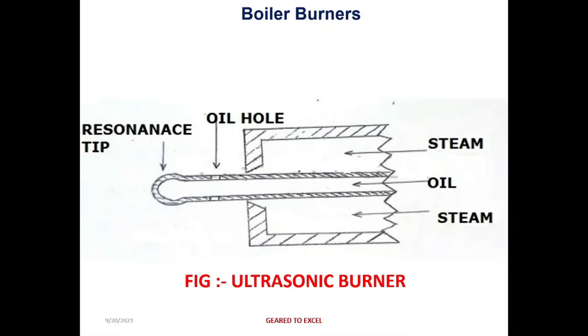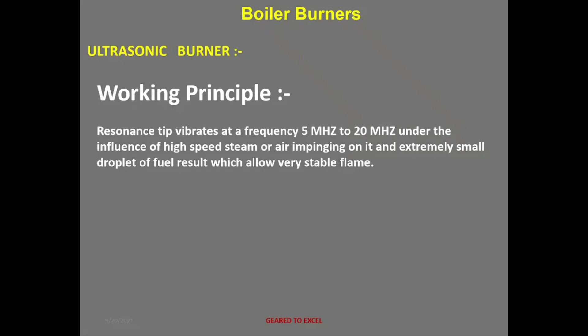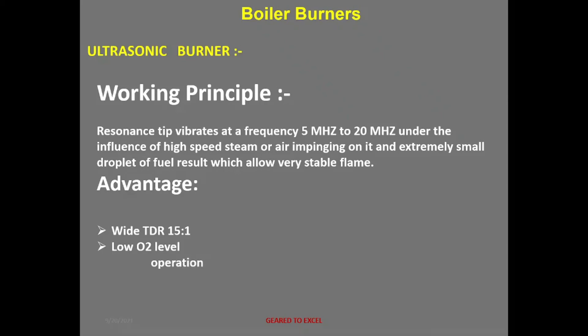The ultrasonic burner has a resonance tip, oil holes, steam inlet, and oil inlet. Working principle: the resonance tip vibrates at a frequency of 5 MHz to 20 MHz under the influence of high-speed steam or air impinging on it, producing extremely small droplets of fuel, which result in a very stable flame. Advantages: wide TDR of 15:1, low O2 level, simple operation, and reduced acid corrosion.